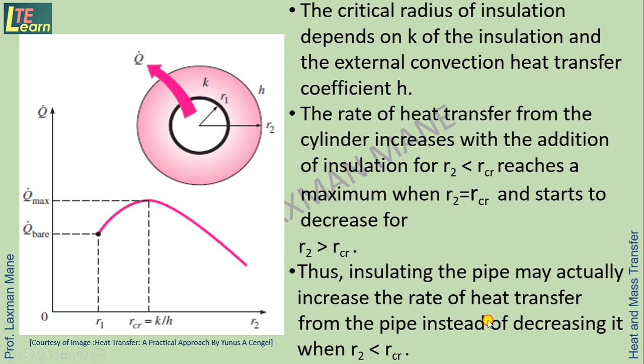The lowest value of h encountered in practice is about 5 watt per meter square degree Celsius for the case of natural convection of gases, and the thermal conductivity of common insulating material is about 0.05 watt per meter degree Celsius. The largest value of critical radius we are likely to encounter is with this formula. So by putting in these values, 0.05, that is the thermal conductivity, and 5, that is the value of h, we get the answer 0.01 meter, that is 1 centimeter. So the maximum critical radius for this value is 1 centimeter.